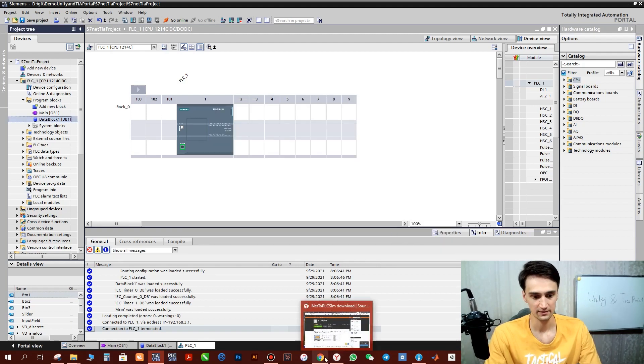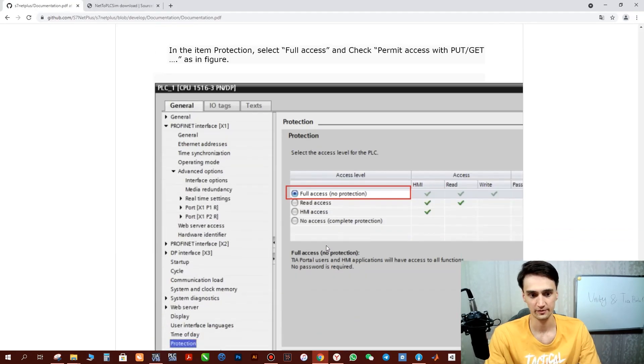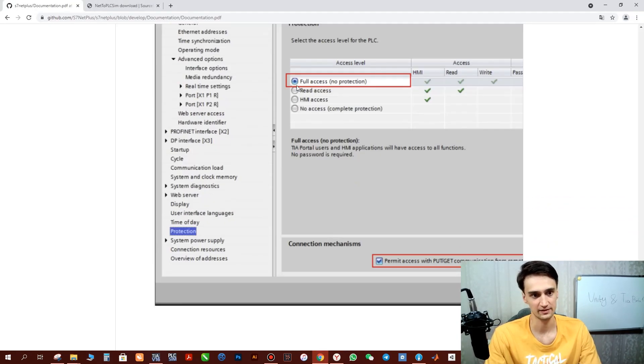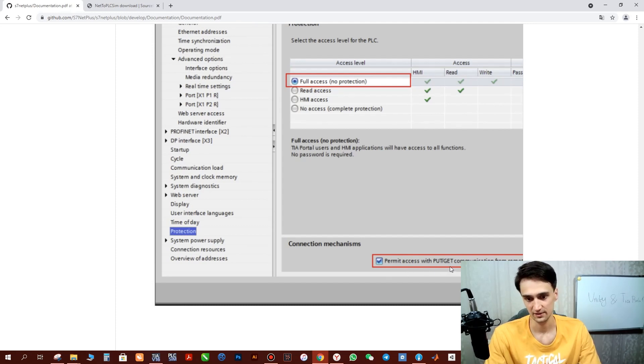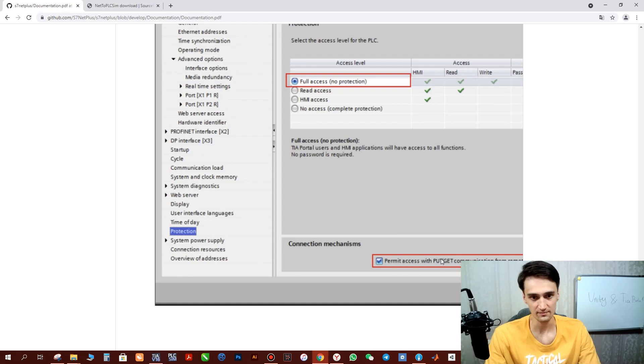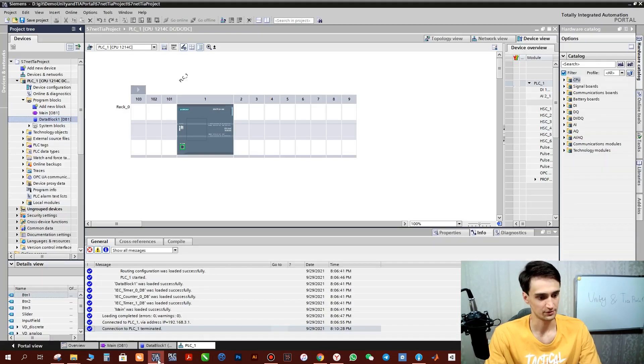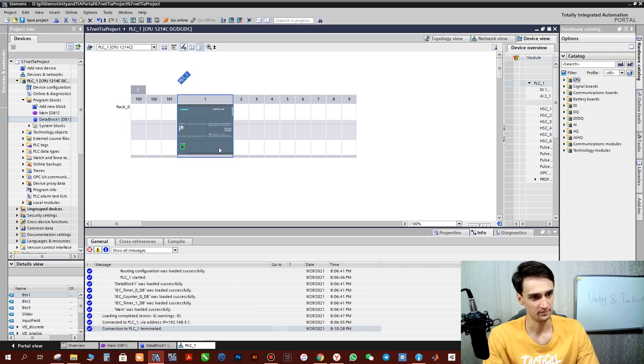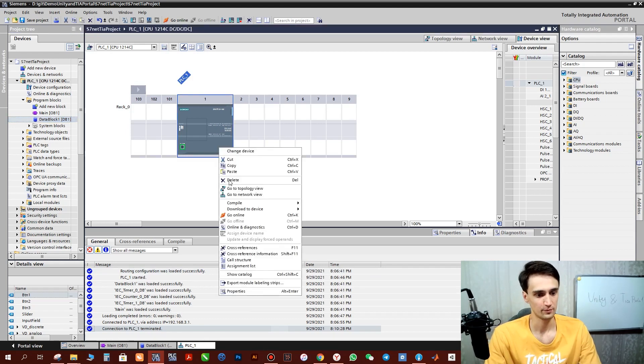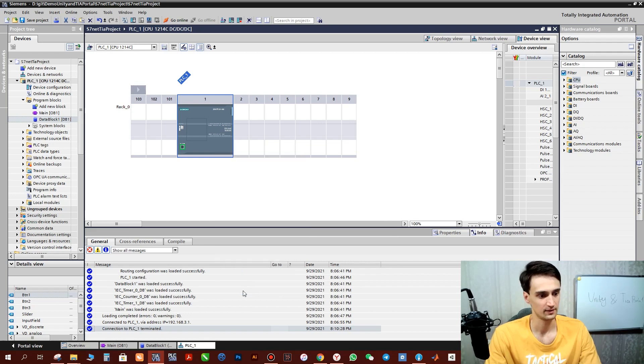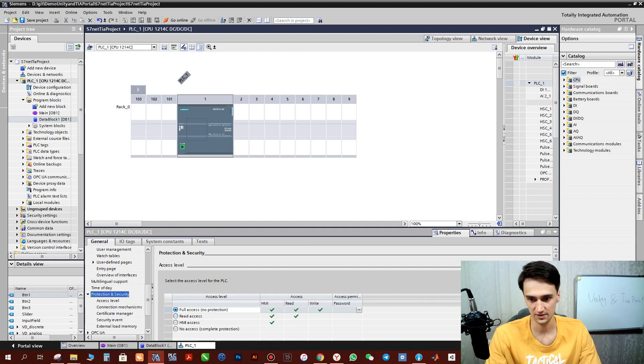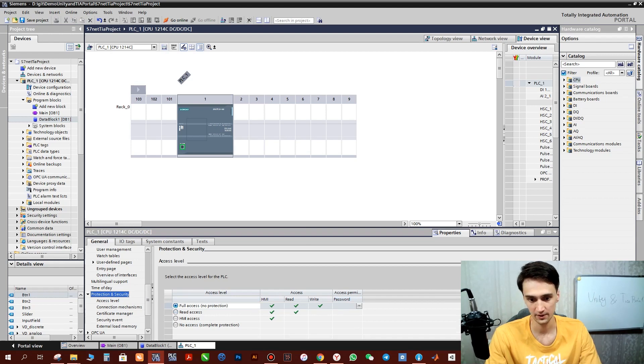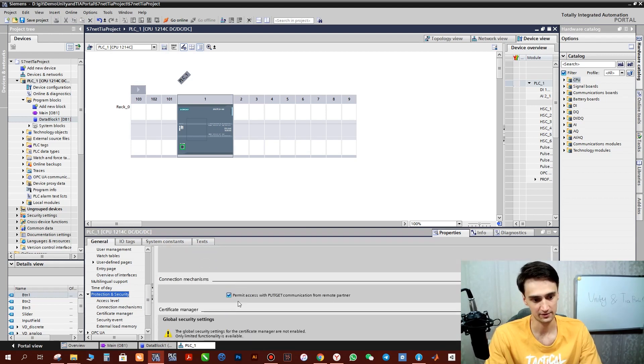Next we have to open PLC properties and provide full access here and also permit access for communication. Open TIA Portal, find PLC, click properties by right button, and protection and security, provide full access. Scroll down and click also here, permit access.